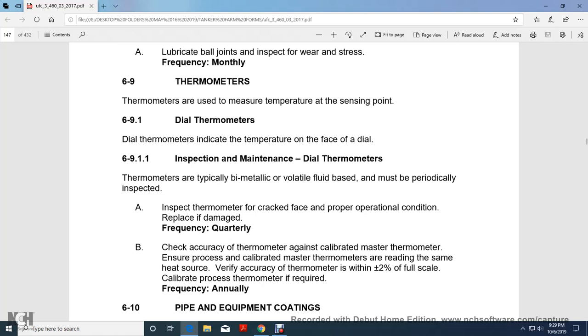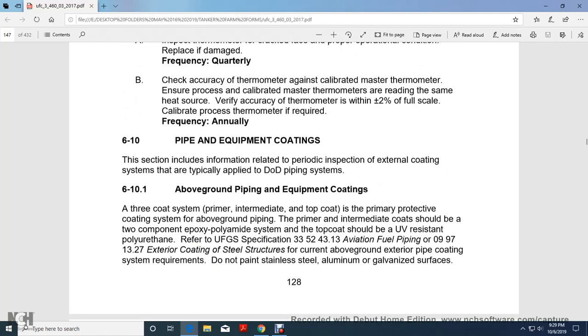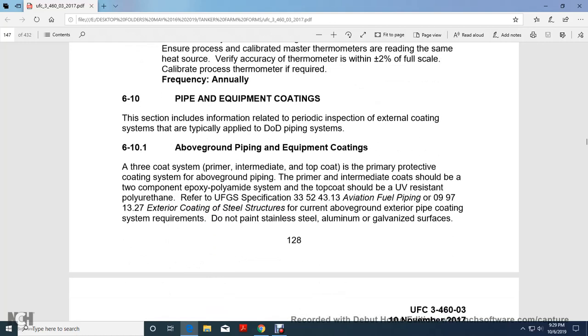Inspect the thermometer face for proper operational condition. Replace if damaged, quarterly. Check the accuracy of the thermometer against calibrated master thermometers. Ensure the calibrated master thermometers are reading the same as the heat source. Verify the accuracy of the thermometer within plus or minus 2% of full scale against the calibrated process thermometer. Required frequency is annually.